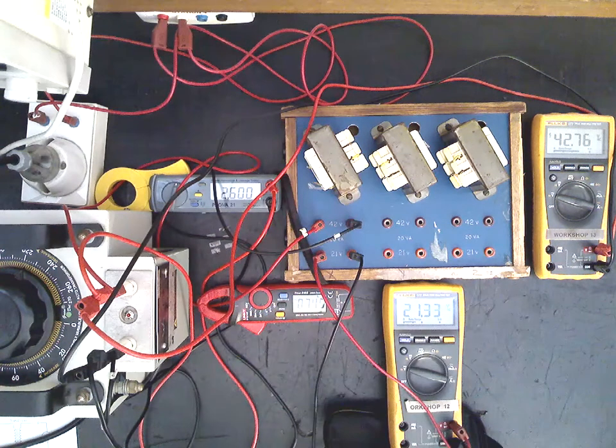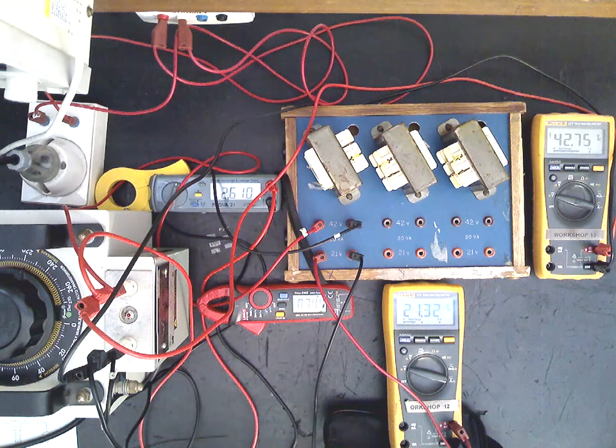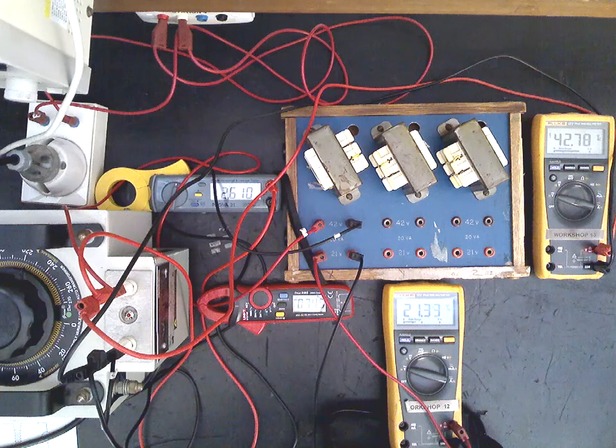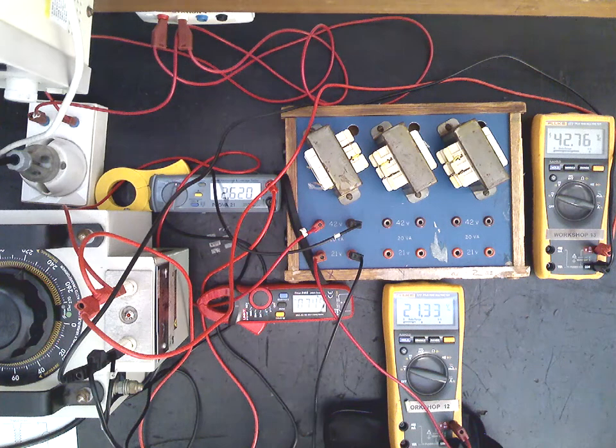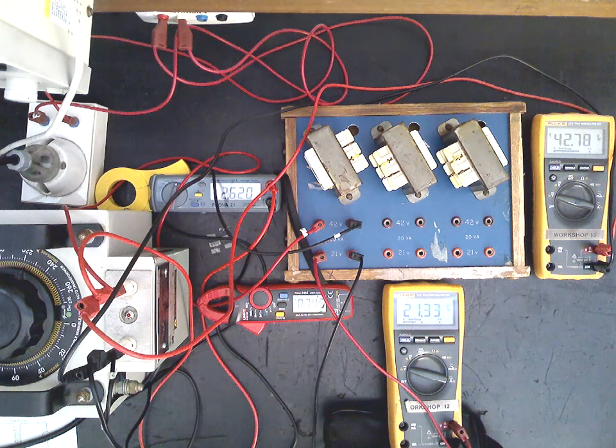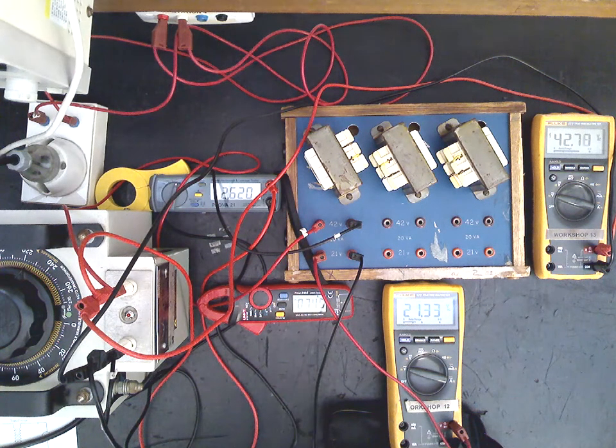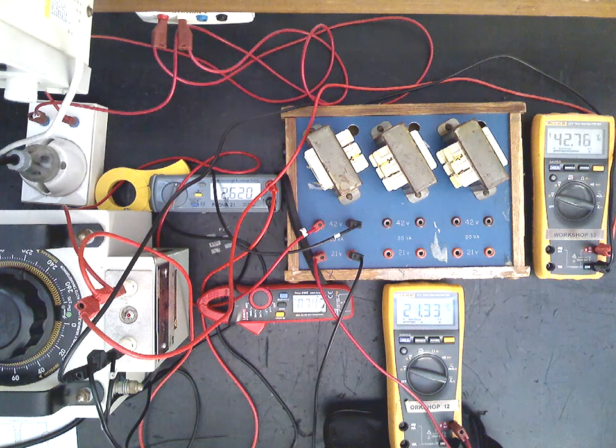is indicating there about 2.6 watts of power loss in the iron circuit of the transformer. So that gives us our iron loss as far as working out efficiency of the transformer.